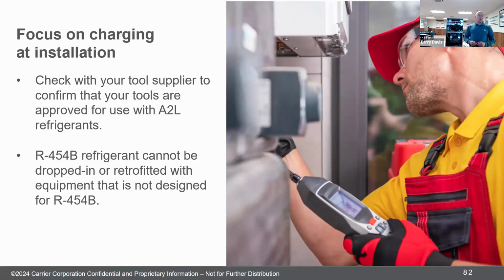Okay, let's look a little bit more at installing. Your tools, all your recovery machines, vacuum pump, digital gauges, leak detectors, all of that, they have to be rated for the 454B refrigerant. Okay, so you need to verify that. If they're not, you'll need to replace that tool with one that is.